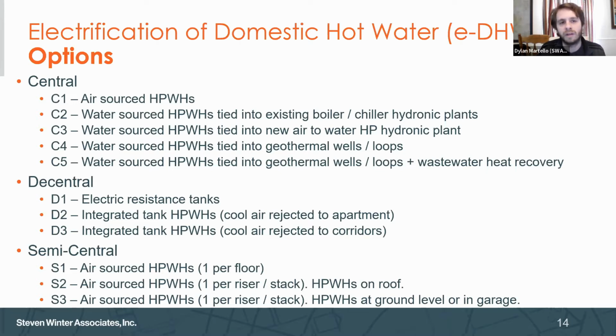So when designing an integrated tank heat pump water heater strategy for apartments, we have to be careful about how they're designed and make sure comfort is considered, because in essence we could end up turning them into electric resistance tanks. We want to be aware of that. But there is a legitimate case for electric resistance if you can couple it with PV, or otherwise offset that energy consumption with renewable energy.